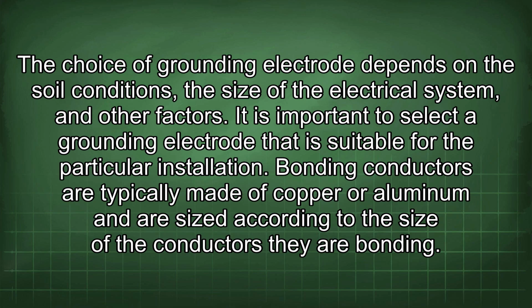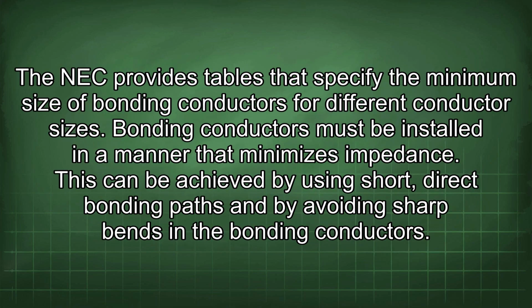Bonding conductors are typically made of copper or aluminum and are sized according to the size of the conductors they are bonding. The NEC provides tables that specify the minimum size of bonding conductors for different conductor sizes. Bonding conductors must be installed in a manner that minimizes impedance. This can be achieved by using short, direct bonding paths and by avoiding sharp bends in the bonding conductors.